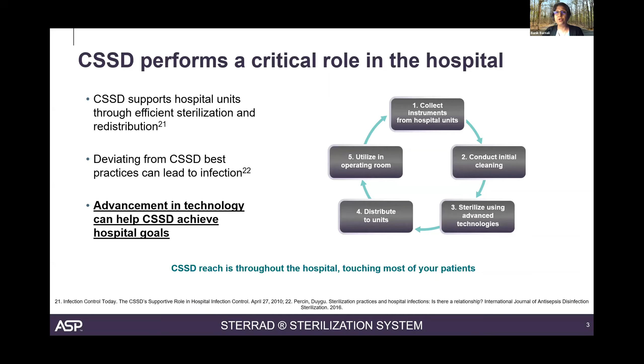One thing for all the viewers here, you need to go back and check the IFUs of the device manufacturer. When I say device manufacturer, I mean the surgical device manufacturer. So say, for example, you have a Karl Storz or you have an Olympus device. The manufacturer of that device will guide you through the reprocessing, what you need to do. Even if you are cleaning, what should be the protocol around cleaning? What kind of chemistry you need to know when you are cleaning the device. We all come with different proposals. We all bring a lot of things to you, but you on the other side of the table need to understand that the device and the sterilizer, when they come together, is when you give out a process.